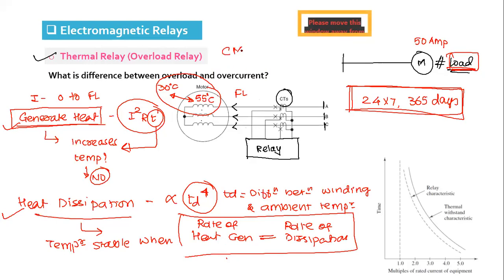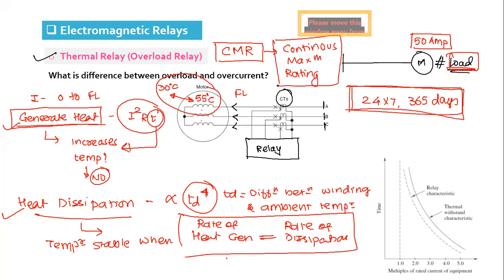And that is what the meaning of CMR is. Suppose if I say 50 ampere is the CMR, it is continuous maximum rating, meaning you can operate that equipment continuously 24/7, 365 days, and it will not have any issue because it is designed for that operation. This motor will draw 50 ampere continuously, and there will be no heat issue, because the insulation you have designed is capable of withstanding the heat generated up to 50 ampere continuously without any problem.